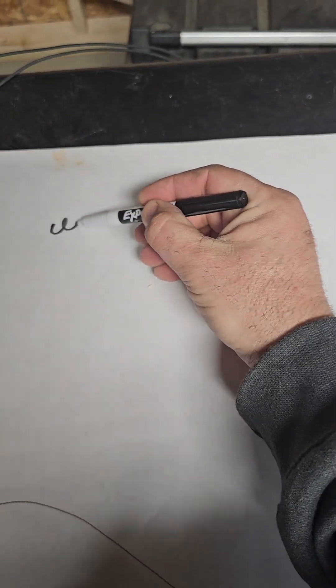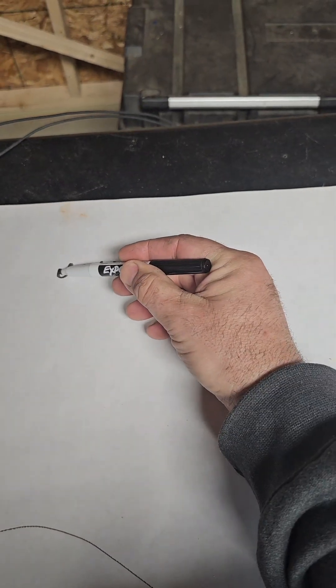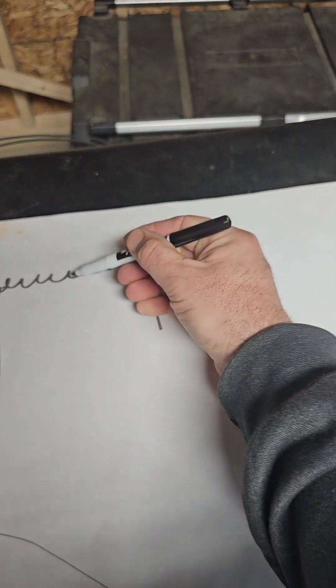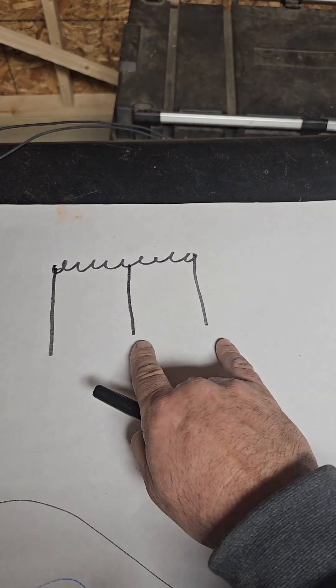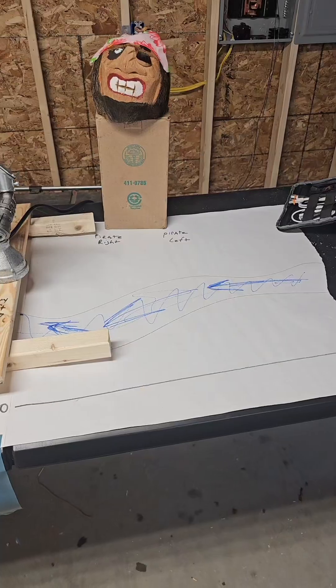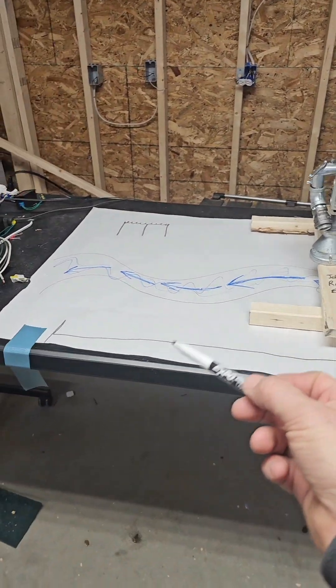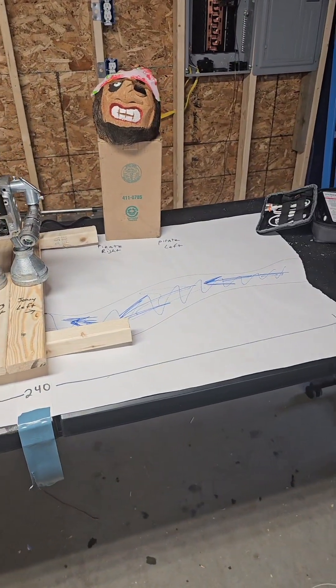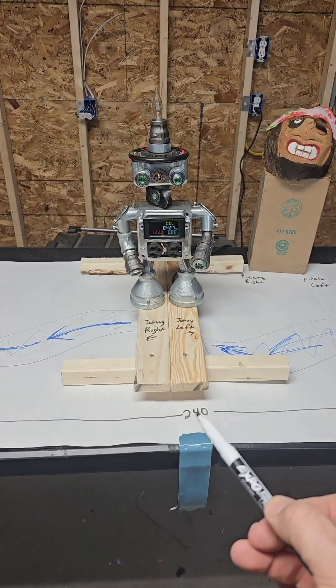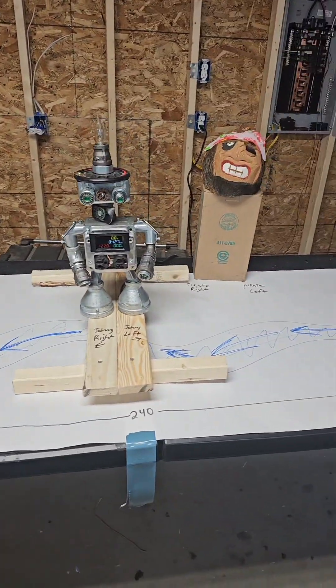The winding in your transformer goes like this: one connection here, one connection here for 240 volts between them, and then we take a connection to the middle for the neutral — 120 volts here, 120 volts here. The neutral is the bridge. So are the two halves on either side of the neutral in phase or out of phase? It depends on your reference. If you're using the neutral as your reference, there are two rivers flowing in opposite directions at half size.